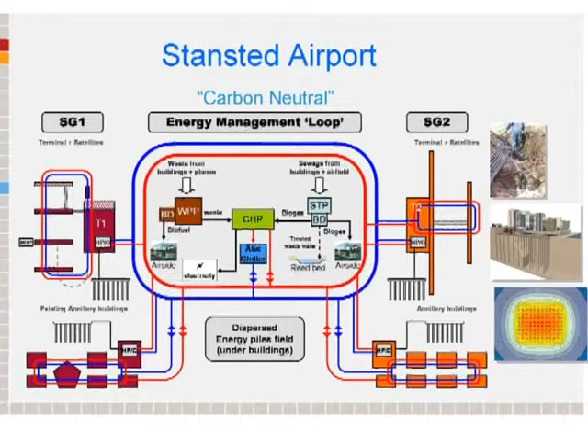So we've got the chillers operating all year round. When there's no cooling demand in the buildings, the cooling is stored in underground piles, which is what this is trying to demonstrate here, and here, and here. Because we've got a constant heating load all year round, we store the cooling when there's no cooling demand, and we use the heat rejected off the chillers to heat the buildings — quite a clever solution.